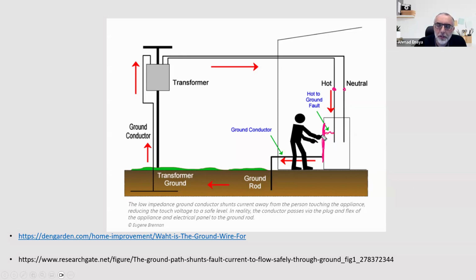That high voltage now has two paths: one through the body of the human, and another with low resistance through a special cable that goes to the ground. In this failure scenario, the path through the human body has high resistance, compared to the direct cable connecting the device to ground, which has low resistance. Which one will the current prefer? The ground.